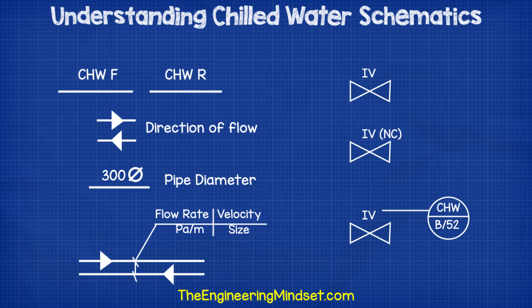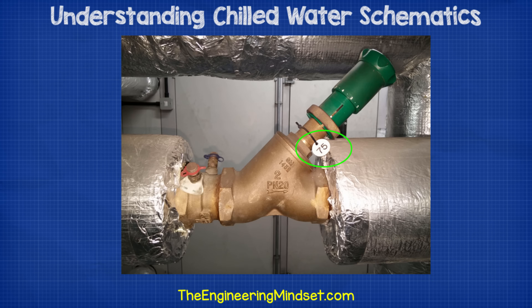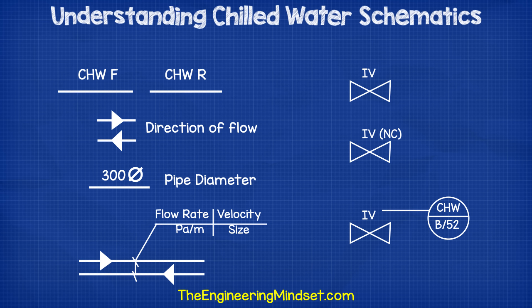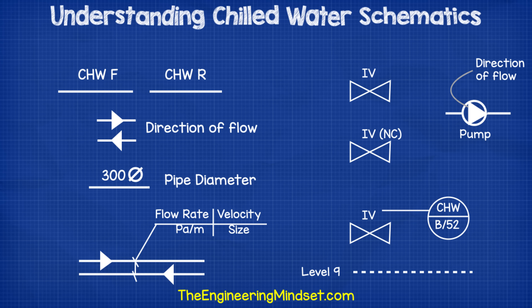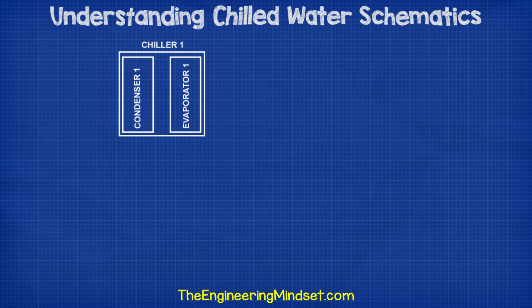The letters NC mean the valve is normally closed. You'll also see little circles around the drawings which have numbers and letters inside — this is a unique ID for the fitting. There should be a matching ID tag fixed to the physical fitting, and you can use the number to find the correct fitting in the system and also look up details for it in a log sheet, such as the type and size. Dotted horizontal lines from one side to the other on the drawing mean that there is a floor there. The arrows on the pumps also indicate the direction of flow.